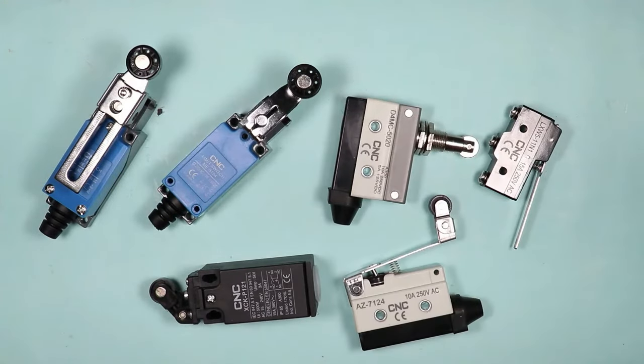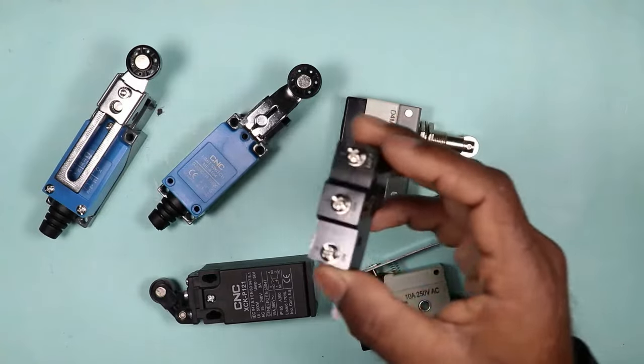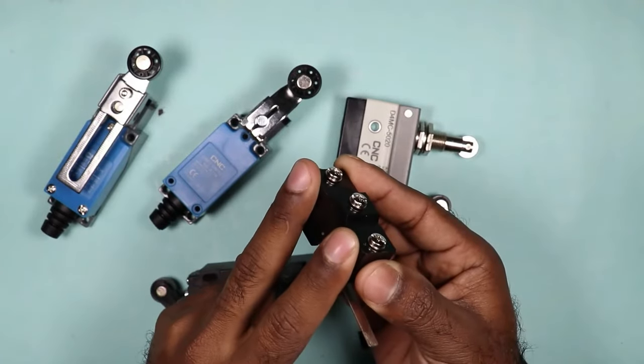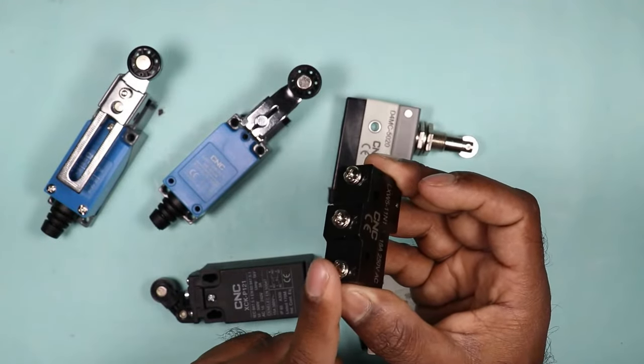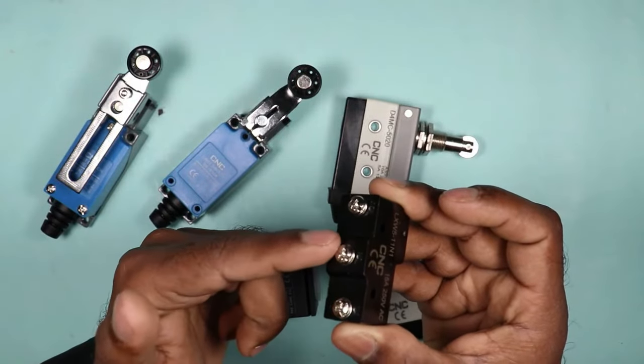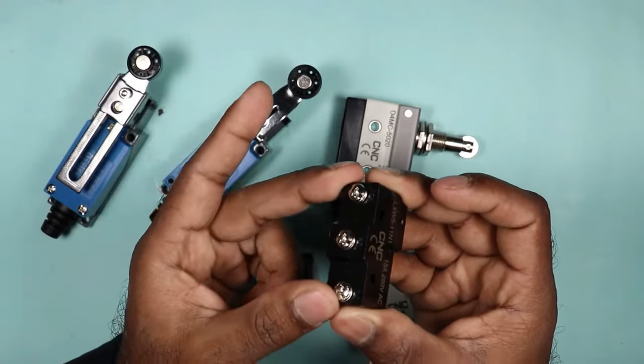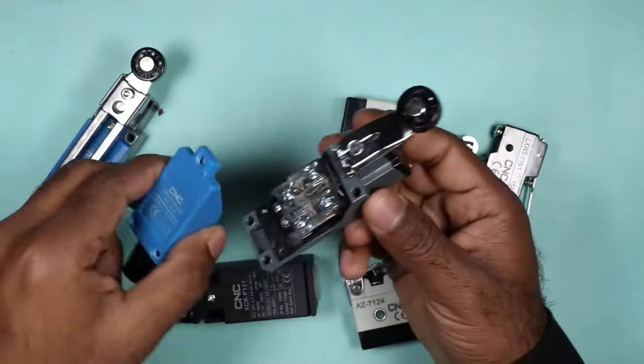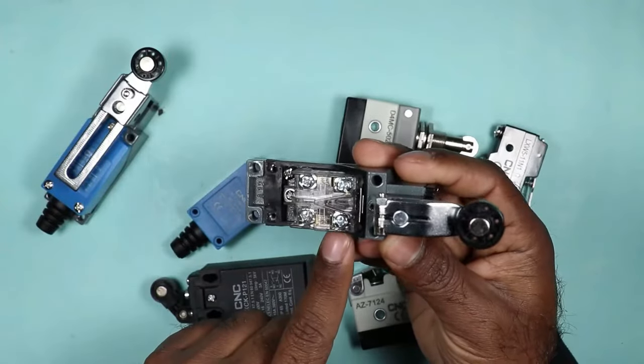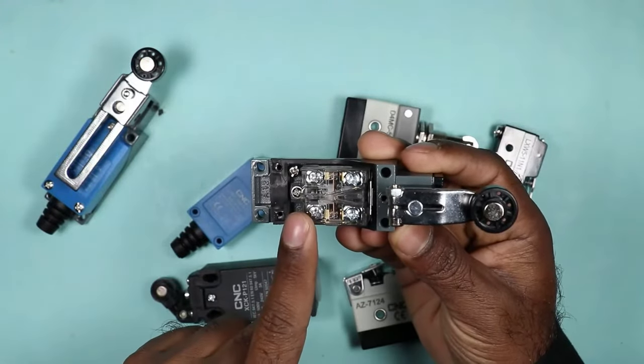For wiring in limit switch, if you look closely, in some limit switch, two terminals are provided. In some limit switch, you will find three terminals. In this limit switch, this point is common, this one is NO, and this is NC. For three terminals, common NO and NC are given. If in your limit switch, four terminals are provided, then two will be NO and two will be NC.